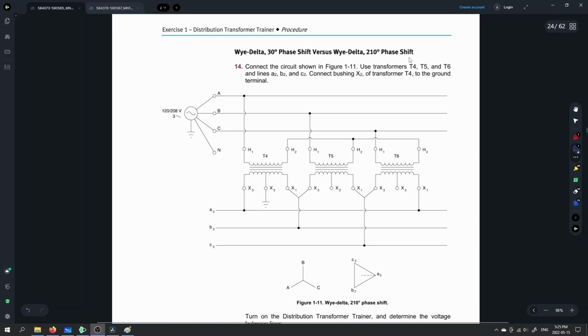Okay, so next one we're doing is the Y to delta 30 degree phase shift versus the Y to delta 210 phase shift. So first thing we need to do is set up T4, T5, and T6 in a Y to delta configuration. So same as we did before on the primary here. So looking here, we have A to H1, we have B to H1 of transformer 5, and then C to H1 of transformer 6. All of the H2s are tied together and they're not grounded. They're just floating there as that center tap.